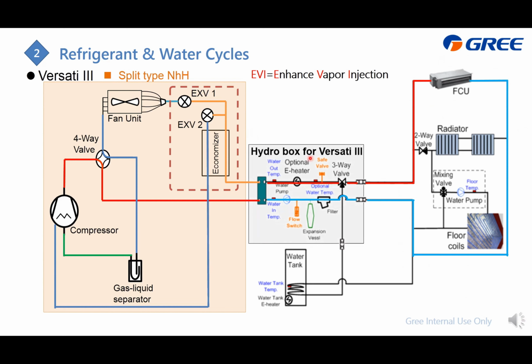Also just take from here, and then after heating up, you go to this built-in three-way valve. Then if we choose to heat up for this one, it is also the same as here. This part is almost the same. And this one is what we call the VERSATI3 hydro box. On site, you just need to connect this 1, 2, 3 for the water system. It's okay. And when we combine the hydro box and the water tank together, it becomes the all-in-one, which is this one. So on site, you just need to install the water piping for the FCU or the radiator and floor coils.